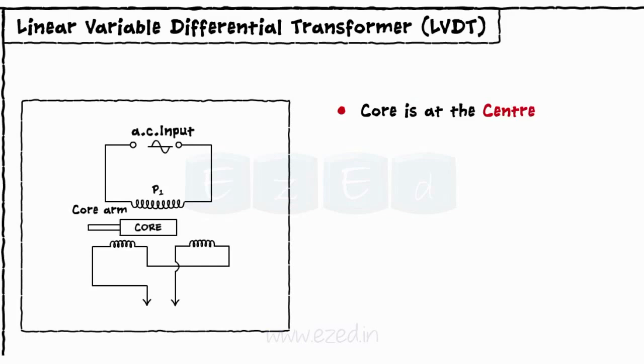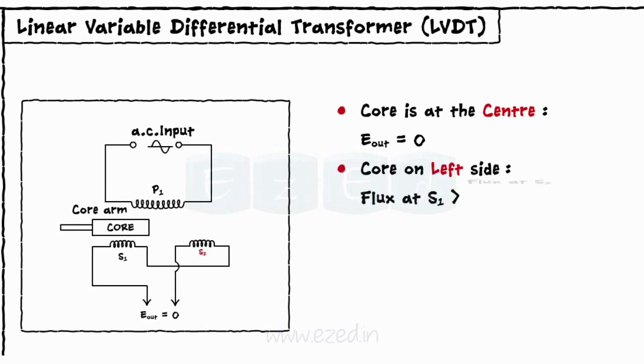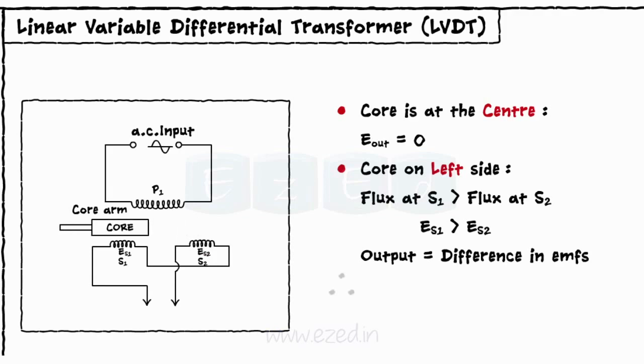Working of LVDT is as follows. When the core is at the central position, the EMF induced is zero. When the core shifts towards secondary winding S1 due to displacement, more magnetic flux gets linked to coil S1 than S2. As a result, the EMF induced in coil S1, ES1, is more than ES2. The output is the difference between the two EMF voltages. Hence, when the core moves towards coil S1, we get output as Vout equals ES1 minus ES2.